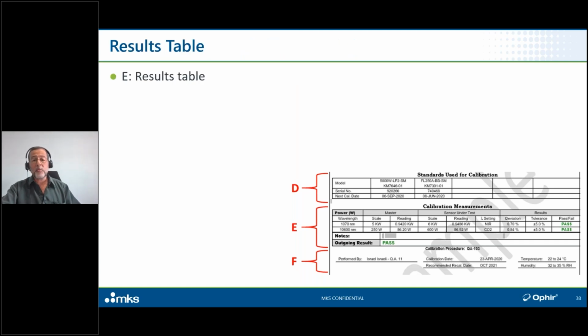E, the results table. Okay, here is where we have all the relevant measurement parameters and the results. In all the C.O.Cs, there will be a results column with the raw data reading of the reference sensor and its settings, what scale, what power scale it was on, what wavelength it was set to, and for the sensor under test, what scale it was set to. It might not be the same model sensor as the reference, so the scales might be different, the wavelength reading and so on. And then the deviation, the tolerance, which means the maximum allowed deviation, and then pass-fail.